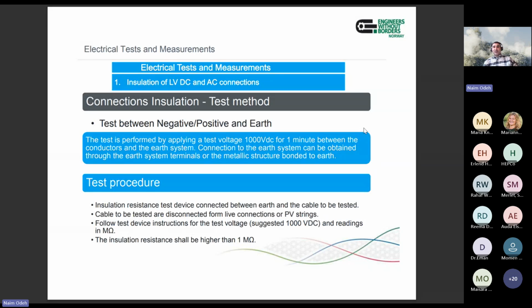Sometimes you do something called a continuity test. This is a basic test that is usually done for cables to make sure that there is no cut in the cable. That's fine, but a continuity test doesn't give you an indication if there is any scratch somewhere in the cable, if there's a touch somewhere at the MC4 connector or somewhere in the structure or in any other location, or sometimes an internal short in any of the modules by mistake or by accident. This is stuff you cannot discover by continuity only, but you need to run an insulation test for the cables to do so.